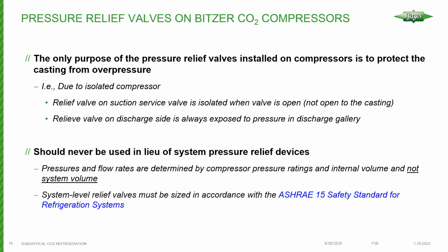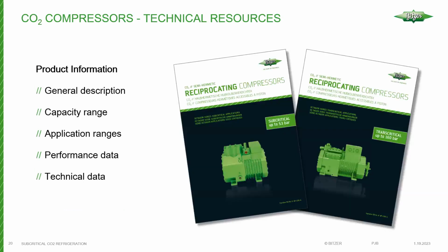And relief valves must always be sized in accordance with the ASHRAE 15 safety standard for refrigeration systems. And we should also refer to any local code and standard requirements that there are. And B52 code is another standard.